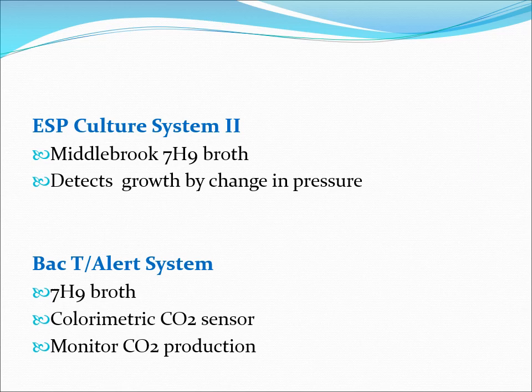The ESP Culture System — remember 'P' for pressure — uses 7H9 broth and detects growth by monitoring changes in pressure as bacteria release CO2. The BacT/ALERT system is based on a colorimetric method: when mycobacteria grow, CO2 is produced, bicarbonate changes the pH, and this brings about a colorimetric change detected by the system.